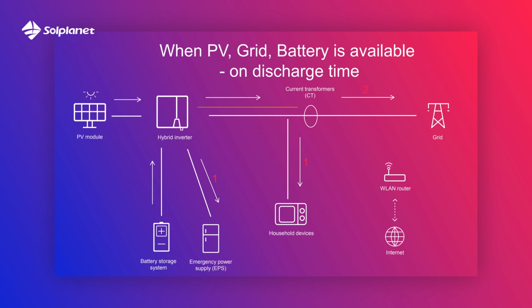On discharge time, solar energy and battery provide power to the loads as first priority. If solar energy and battery are sufficient to supply loads, and if there is still some extra energy, then the excess power from solar energy and battery will be delivered to the grid at the same time.